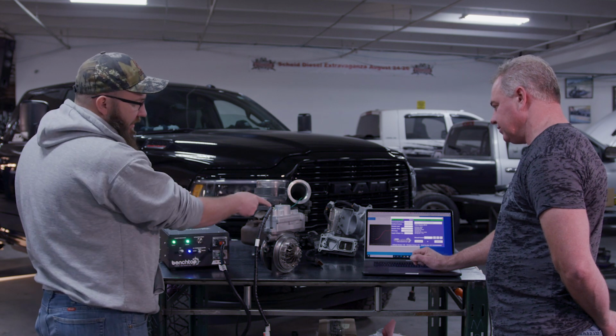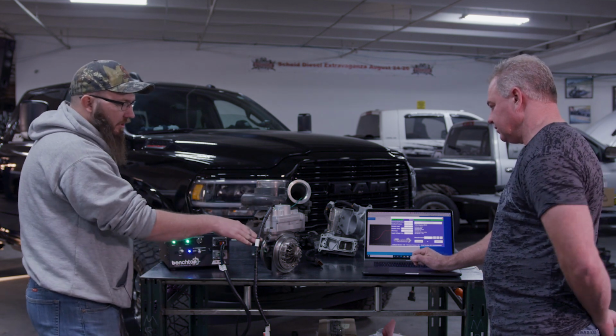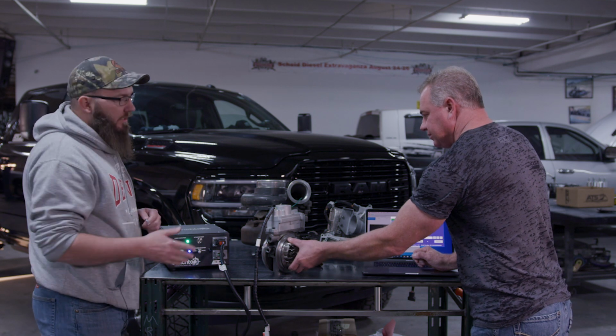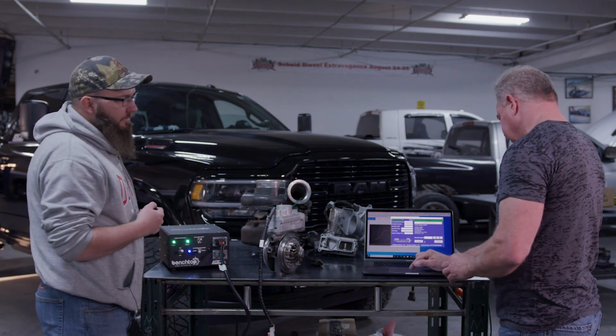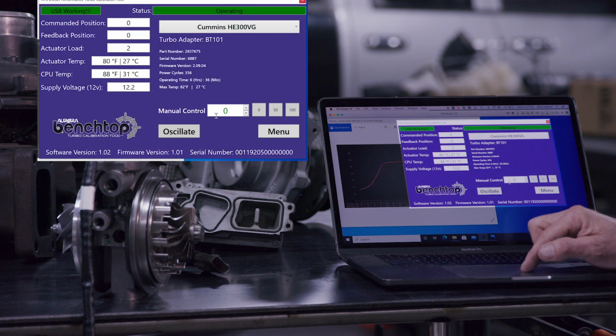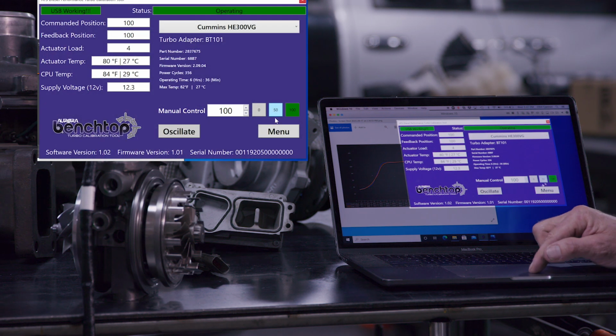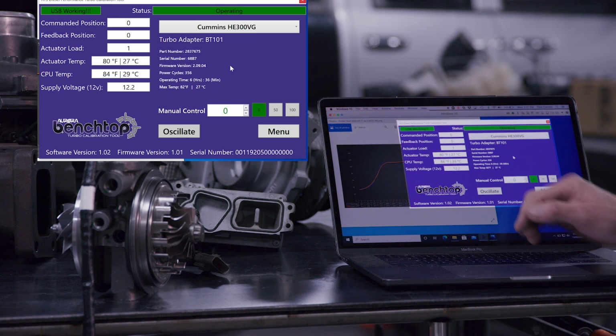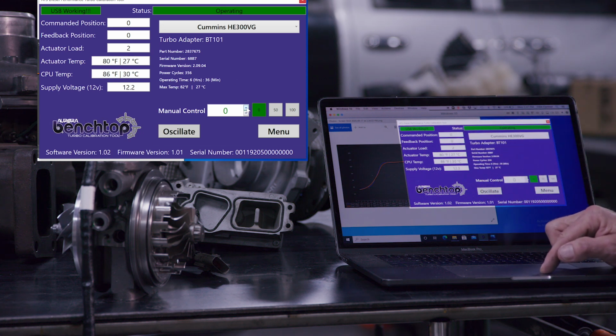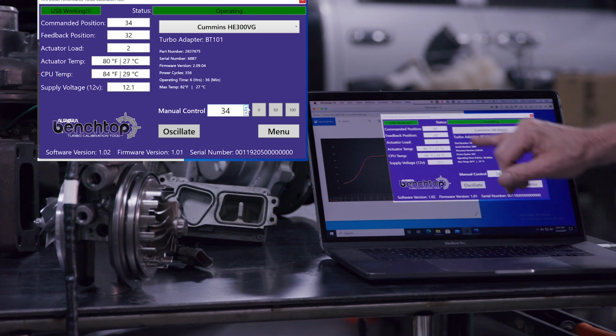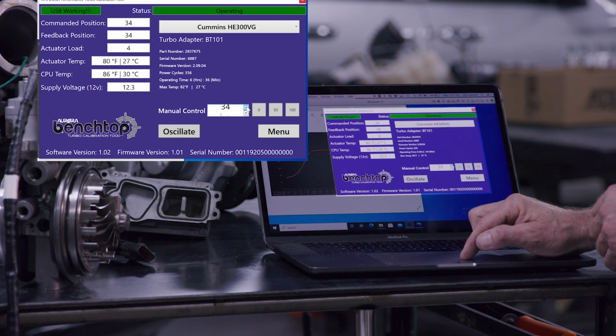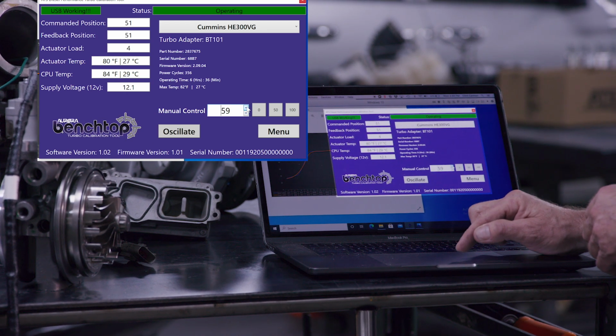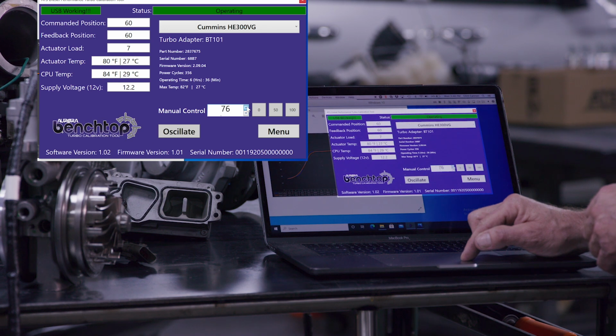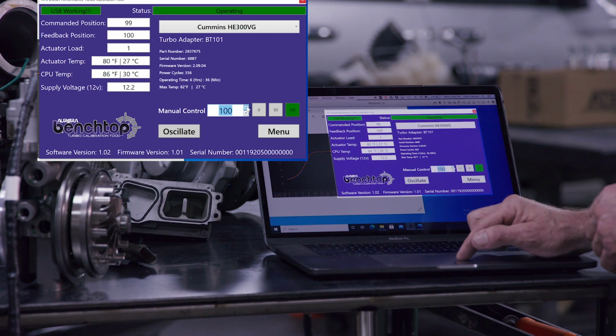Now we can do a demonstration with that actuator without the center cartridge, and you can see that it'll actually go over its range, and it'll actually tell you that there's an error. So in the software itself, it basically shows you can go like 0%, 100%. Now the important thing to look at here is as you're increasing the commanded, you want to make sure that your commanded and your actual is the same. So when you go up to 100%, as long as what we're commanding the actuator follows the actual, then you've got a controller that's good and you have a turbo that's not sticky.